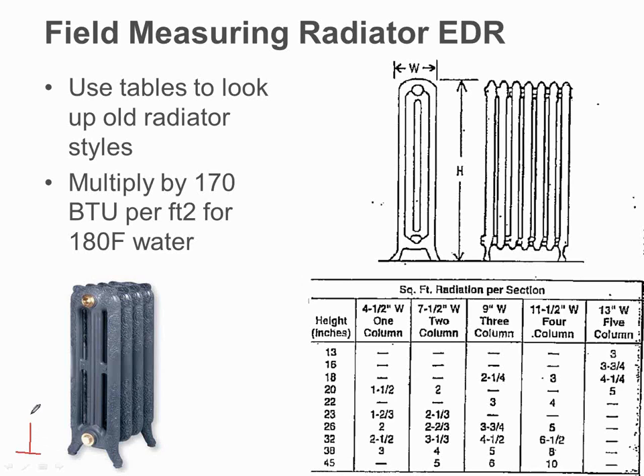You can measure the width, or you can count the number of tubes or columns, however they want to call it. Then you go over to one of these charts, and it'll say, for a 20-inch high radiator with 2 columns, I'm going to have 2 square foot of radiation per section. Now in our little radiator here, I times it by the 4 sections, and that tells me basically I have 8 square foot of radiation.